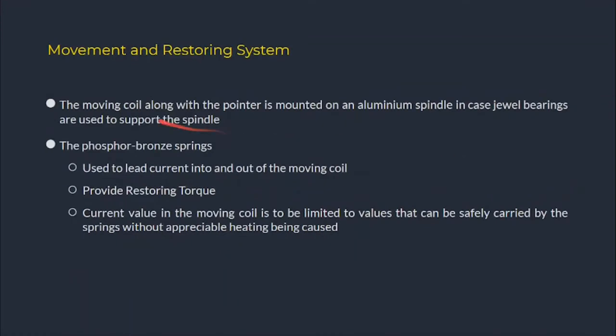The moving coil along with the pointer is mounted on an aluminium spindle. Jewel bearings are used to support the spindle. Phosphor bronze springs are used to lead current into and out of the moving coil and they provide the restoring torque. The current value in the moving coil is limited to values that can be safely carried by the springs.